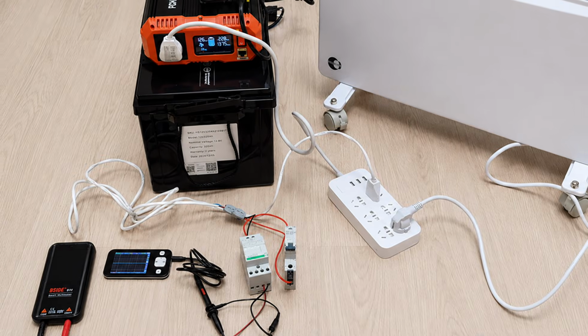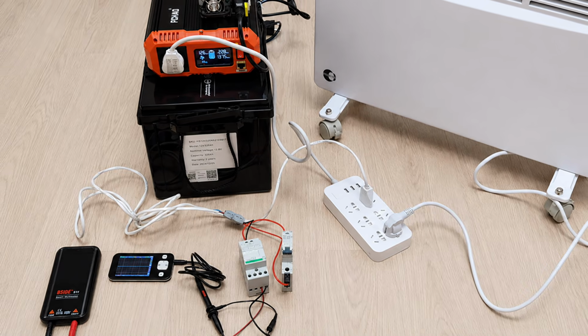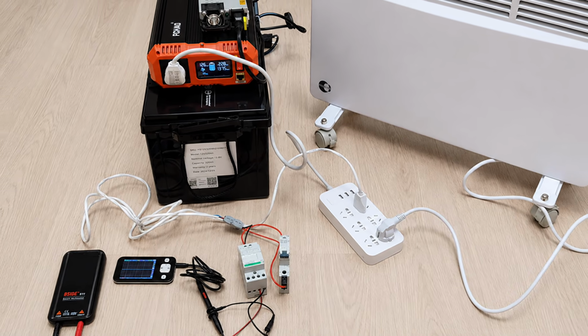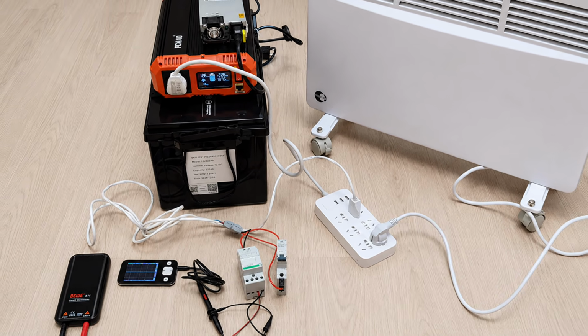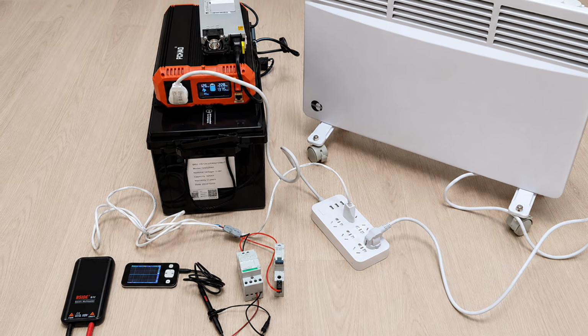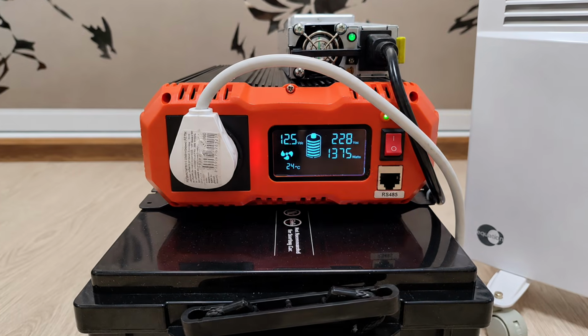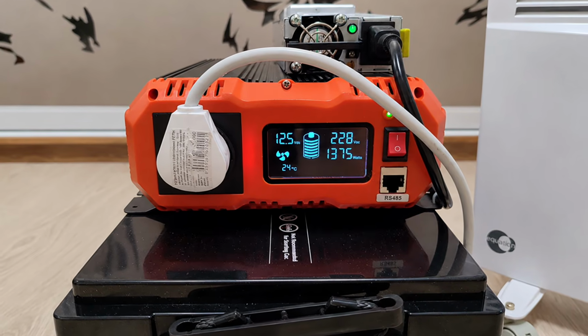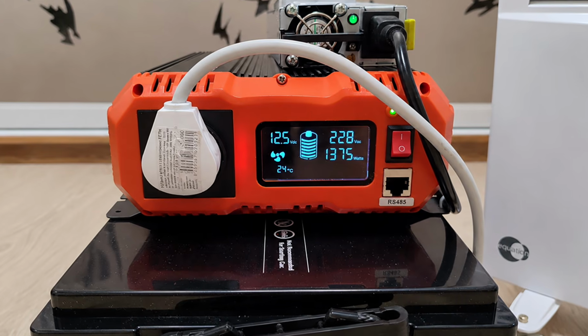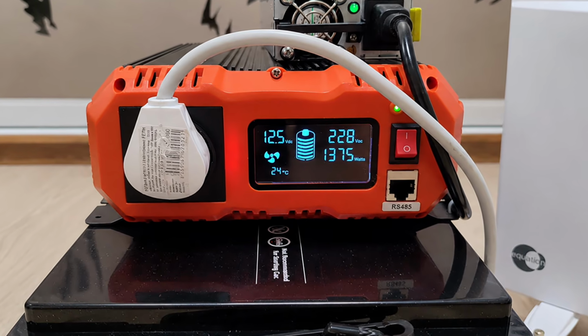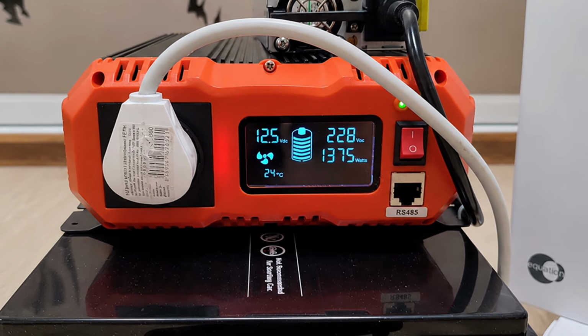Now let us complicate the situation a little and take measurements under load. I decided not to do this halfway, but to load it seriously, using a heater for that. The power is 1,375 watts. Here the constant forced cooling is already running, although at the start the temperature is still low, 24 degrees.